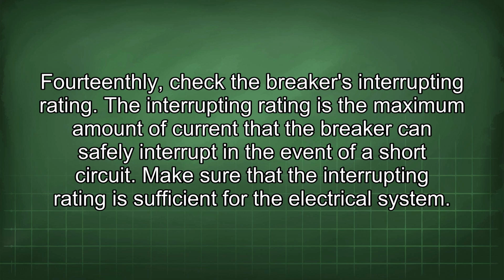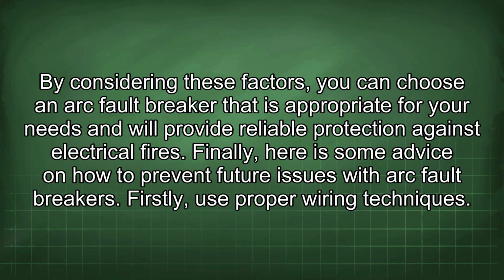14thly, check the breaker's interrupting rating. The interrupting rating is the maximum amount of current that the breaker can safely interrupt in the event of a short circuit. Make sure that the interrupting rating is sufficient for the electrical system. By considering these factors, you can choose an arc fault breaker that is appropriate for your needs and will provide reliable protection against electrical fires.